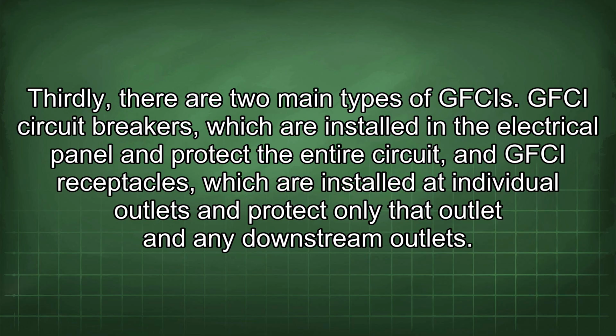Thirdly, there are two main types of GFCIs. GFCI circuit breakers, which are installed in the electrical panel and protect the entire circuit, and GFCI receptacles, which are installed at individual outlets and protect only that outlet and any downstream outlets.